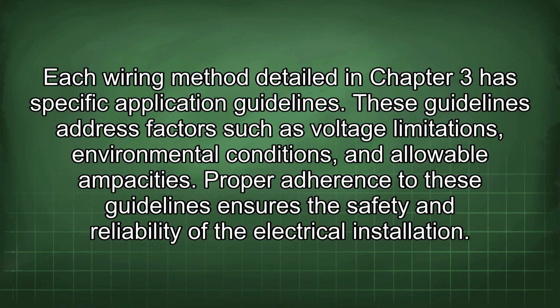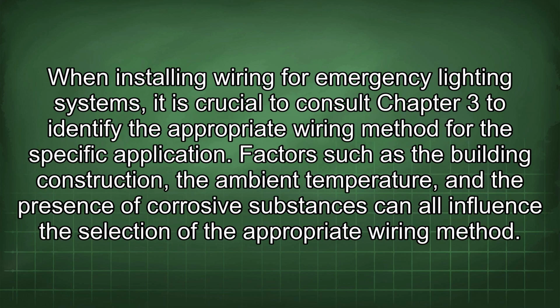Each wiring method detailed in Chapter 3 has specific application guidelines. These guidelines address factors such as voltage limitations, environmental conditions, and allowable ampacities. Proper adherence to these guidelines ensures the safety and reliability of the electrical installation. When installing wiring for emergency lighting systems, it is crucial to consult Chapter 3 to identify the appropriate wiring method for the specific application. Factors such as the building construction, the ambient temperature, and the presence of corrosive substances can all influence the selection of the appropriate wiring method.